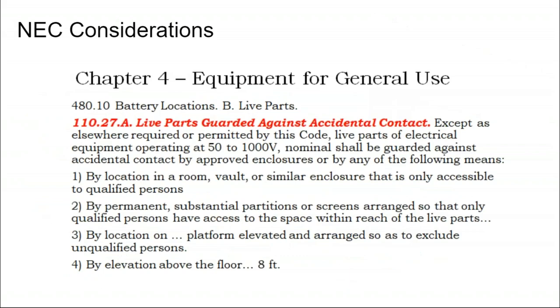So, guarding the batteries—and in some cases, especially when using cheap parts, not just the batteries but the battery inverters and the rest of the equipment should be guarded against accidental contact. That might mean the room needs to be locked. If you're planning on putting your battery room in a utility closet, but it's a large laundry room, you need to think about who's going to be in that laundry room. Are unqualified people going to be in there? That might mean it's time to give the system its own physical barrier for protection.